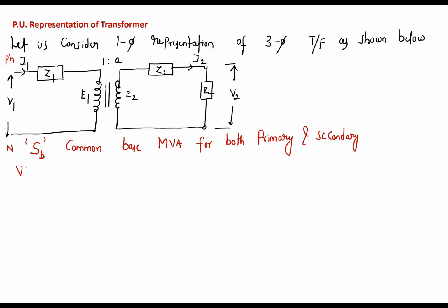Now let VB1, IB1 and ZB1 be the base voltage, base current and base impedance on the primary side. Similarly, let VB2, IB2 and ZB2 be the base values on the secondary side. Understood? Why don't we have two different base MVAs? Because the machine rating is the same from primary or secondary. So the machine will have a common base MVA rating, whereas the other base values will be different on the primary and secondary sides.